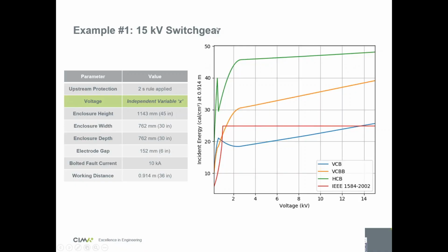So let's put typical values for 15 kV switchgear: a fault current of 10 kA and a working distance of 36 inch. What's the impact of the voltage on the energy? The energy is the y-axis and the voltage is the x-axis. The blue curve is VCB, the orange curve is VCBB, the green curve is HCB, and the old version of the standard is in red. So what's the difference between them? You see HCB, for any voltage, is much higher than VCBB and VCB, and the old version of the standard is about in the middle.